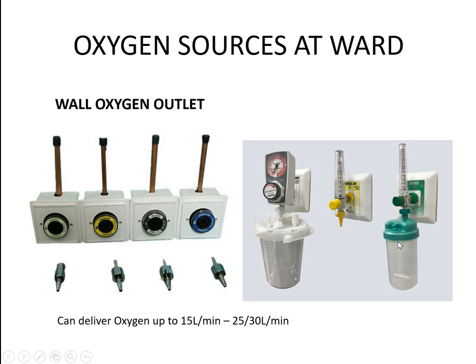This part of the regulator is called the flow meter. If you can see, it has some readings, and with it we can manipulate the flow. It starts from 0 and goes up to 15. So with this particular flow meter, we can deliver 15 liters per minute of oxygen to the patient. Whereas this one goes from 25 to 30 liters per minute. That depends on the various flow meters.